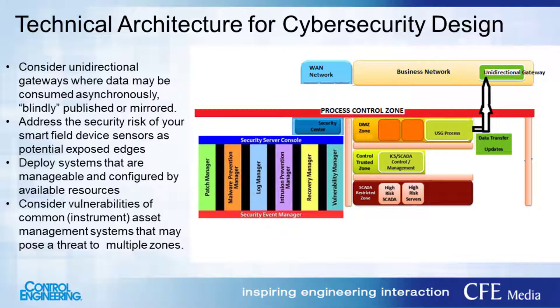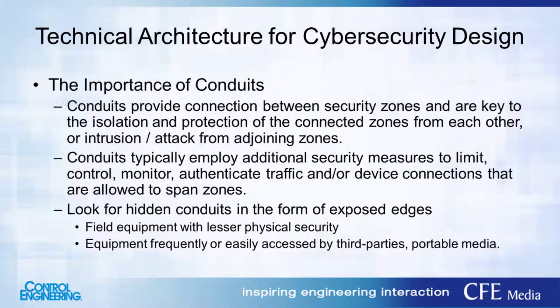There's an increasing need for process data to be available on the business, cloud, or analytical environment. Use data diodes, configure your digital sensors properly, and design and implement any wireless mesh network for smart device systems carefully. Ask vendors for references from other installations to get end-user feedback. Conduits are the interconnections between different zones — they're important both as points of protection and monitoring, but also be aware of hidden conduits. Those hidden conduits are often the means that get compromised — the connection you didn't think about between systems that someone uses as a pivot point for an attack.